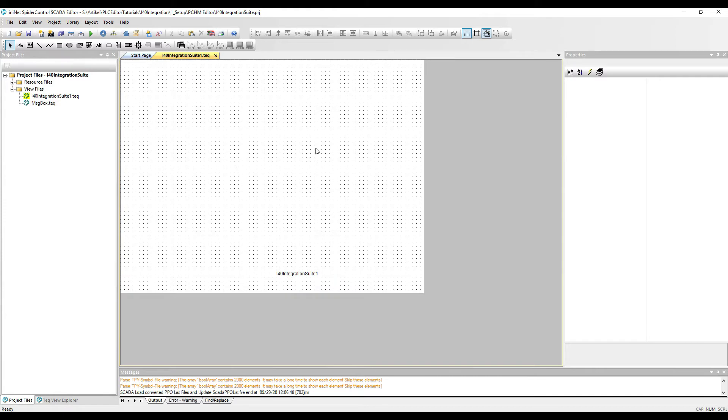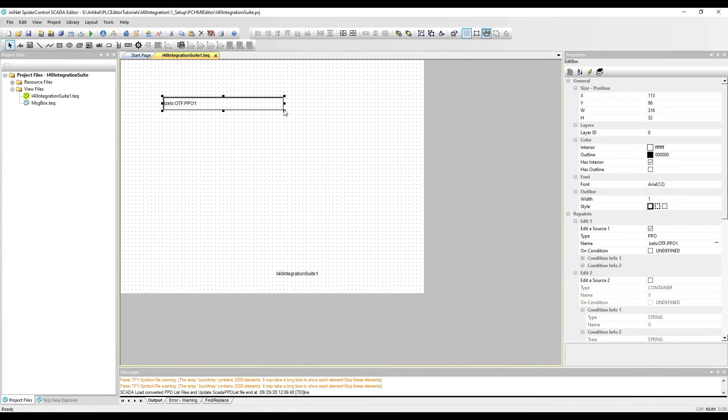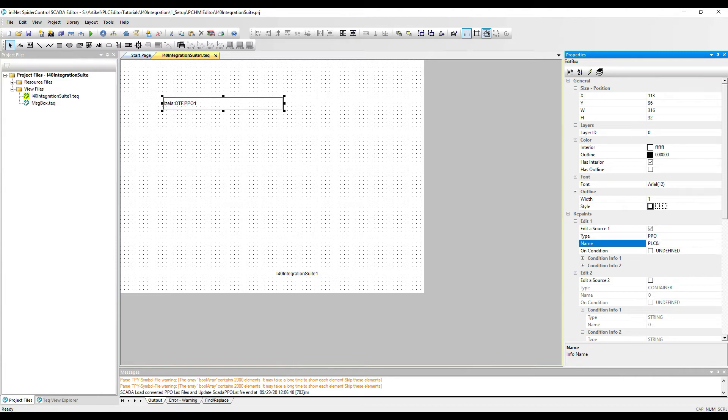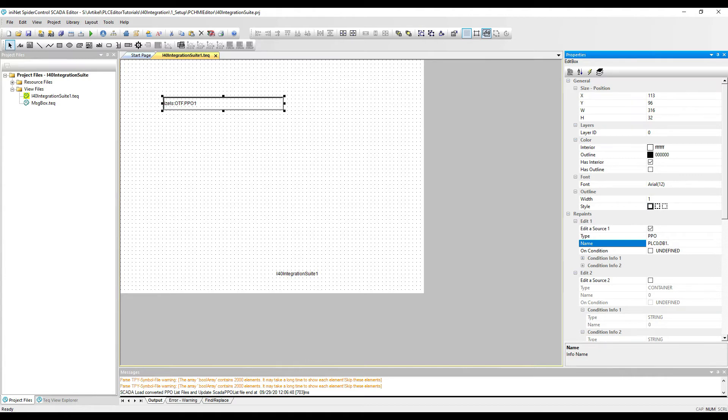And we will open the first page of this HMI just to enter a few edit fields to see if we can already access the variables from PLC. So the first variable which we would like to have a look at is located on the SIMATIC. So the driver is called PLC0, and for the ISO on TCP driver we will use a direct DB notation. So the name will be DB1DBW0.